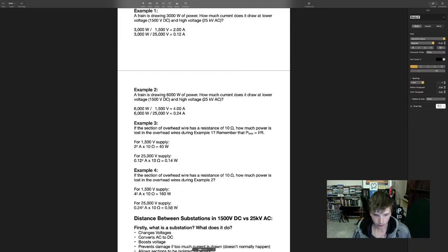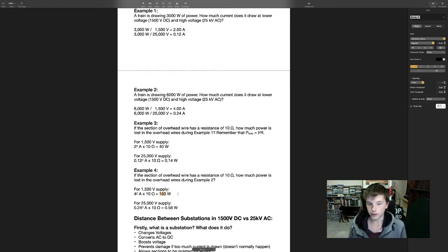The point is that even with the higher power, much higher current, powered train, we're still losing less than a watt of power in the 25 kilovolt overhead supply, versus the 1500 volt power supply where we're losing now 160 watts. That is one of the biggest reasons why 25 kilovolts is a more popular voltage these days - there's a lot less power lost in the wires.